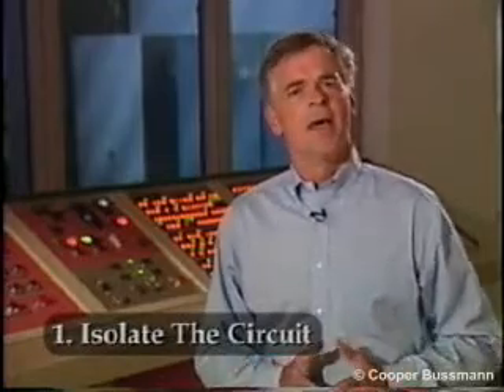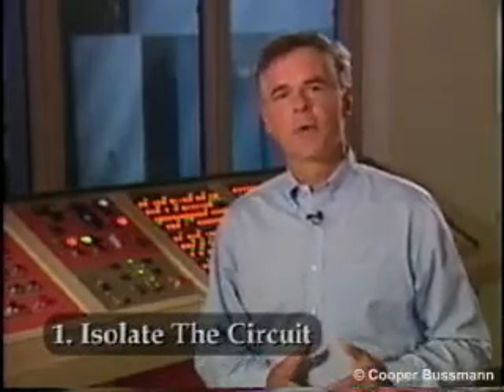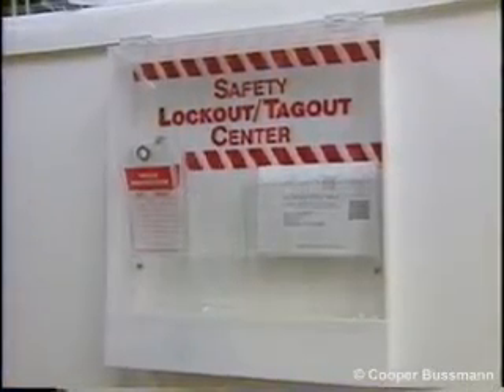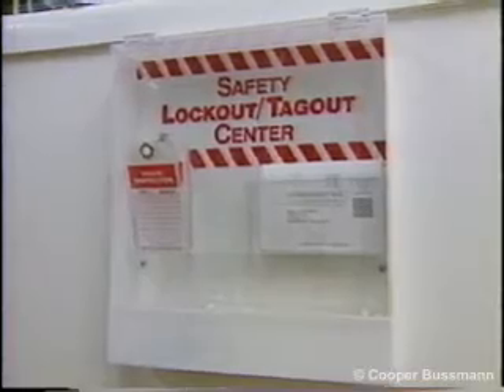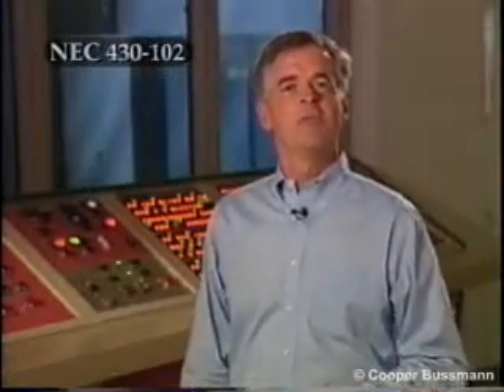Isolate the circuit. Electrical systems must be designed to support preventative maintenance with easy access to the equipment. Designers need to make it easy to isolate equipment for repair with a disconnecting means that provides for proper implementation of lockout-tagout procedures. A sound design should also provide optional disconnecting means at all motor loads. This is in addition to the disconnect required at the controller that can be locked in the open position. Disconnects at the motor will provide improved isolation and safety for maintenance and for use in case of an emergency.